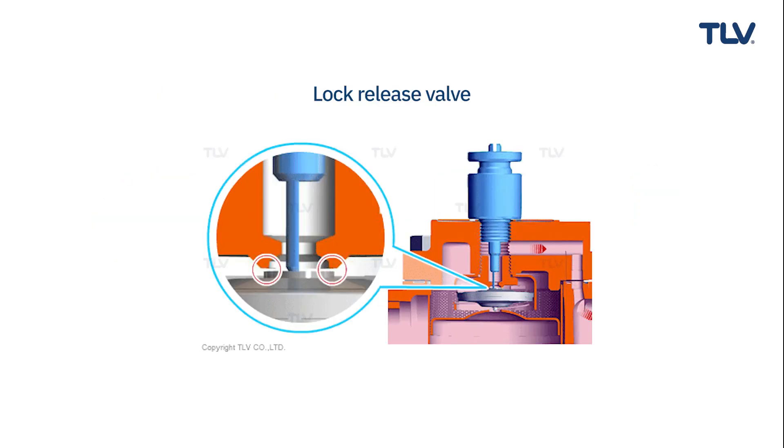A lock release valve uses the automatic venting feature of a steam trap, such as an X element, to forcibly open the valve and release steam to the outlet side of the trap, fixing the steam locking problem.